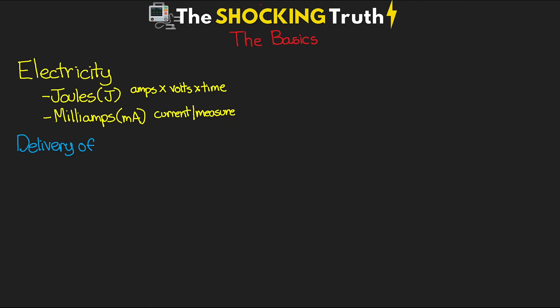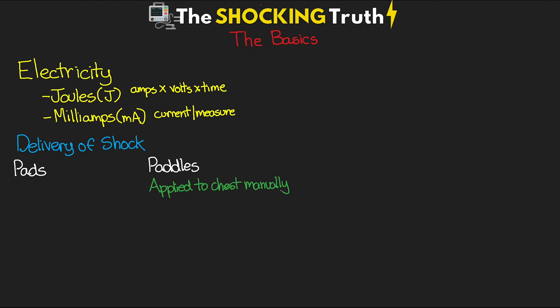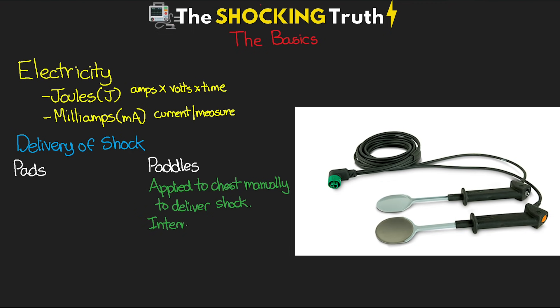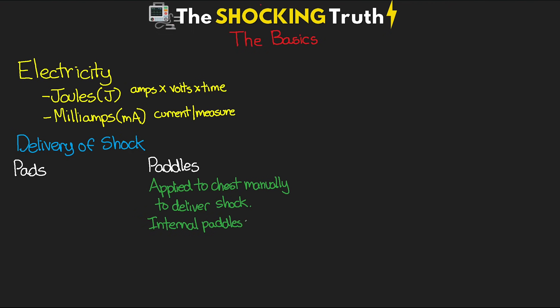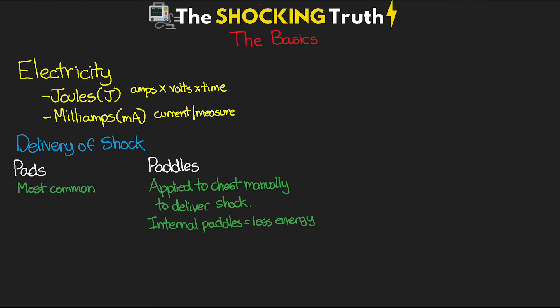Now let's talk about the delivery of the shock — how we get the electricity to our patient when needed. There are two main ways: paddles or pads. Many defibrillators have paddles attached to the side of the device, made famous by movies and TV shows, and these are applied to the chest manually to deliver the shock. There are also internal paddles that can be used directly on the heart and require much less energy. Pads are by far the most commonly used in the hospital today, as they're quick to place and often already attached to the defibrillator.